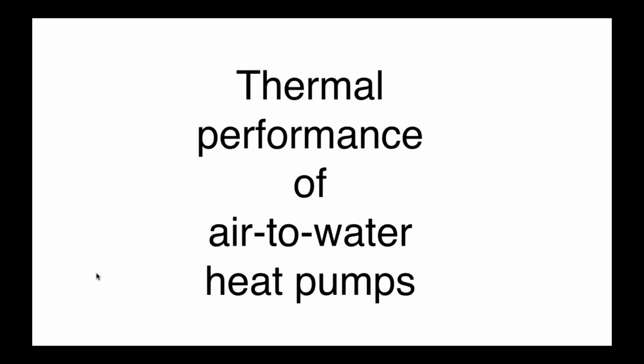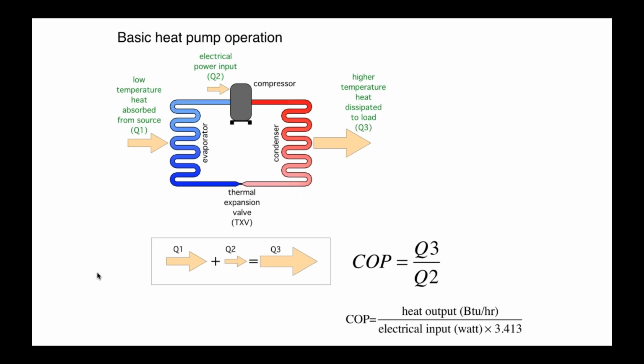All right, let's talk about thermal performance. All right, basic operation of any refrigeration circuit. We're going to absorb low-grade heat at our evaporator. That causes the refrigerant to evaporate to a vapor. It's going into a compressor. Compressor is going to bring up pressure and temperature. We're going to send the hot refrigerant gas through the condenser. It's going to transfer its heat off. In the case of air to water, it's going to transfer it to the water stream. And then finally, that refrigerant is going to go back through an expansion device, and that returns it to the same condition where it's ready to make another pass through the evaporator.